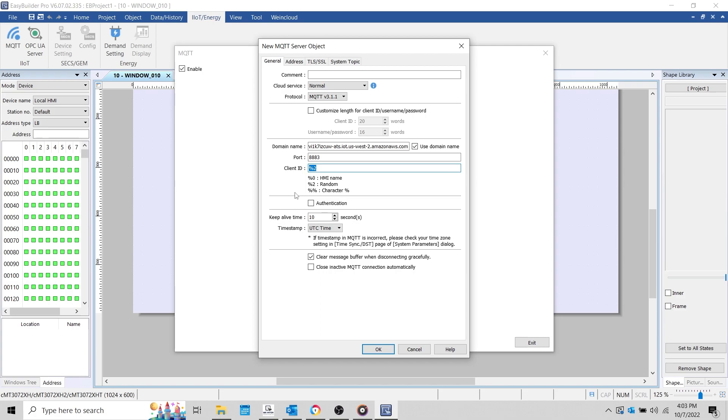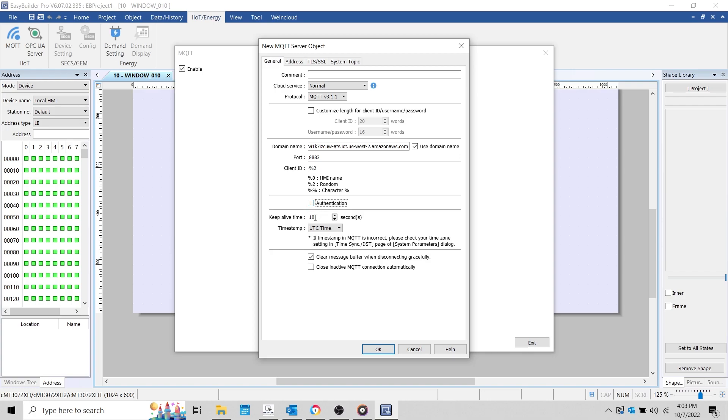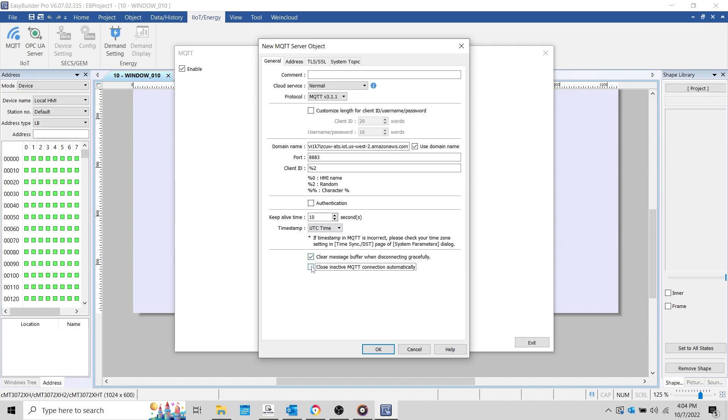Now, there are some additional parameters here that we won't need to modify during this demonstration. This includes authentication, which will allow you to enter a username and password when connecting to an MQTT broker. Keepalive time specifies how long the server will wait before identifying the HMI as disconnected. The timestamp can be sourced from UTC time by referencing the HMI's time zone settings or from the HMI's local time. Clear message buffer when disconnecting gracefully will clear the MQTT message buffer. The buffer can hold up to 10,000 messages, and a buffer usage address can be configured within the address tab. Close inactive MQTT connection automatically will disconnect the HMI from the server while it is inactive for a given period and reconnect the HMI when it is ready to publish data.